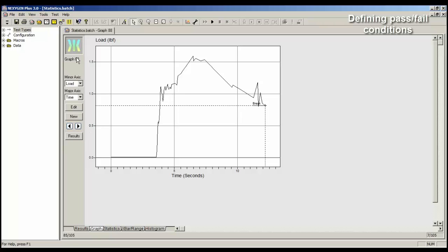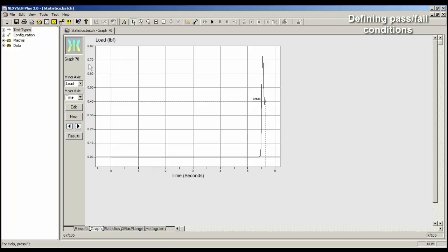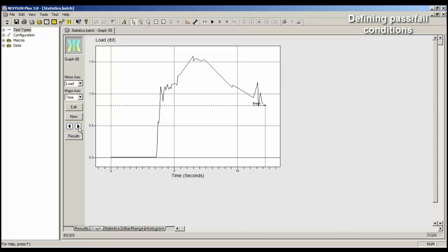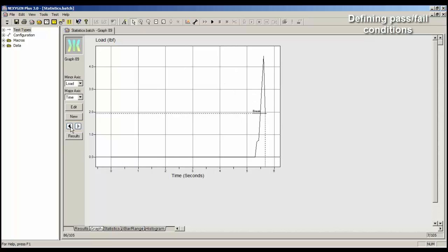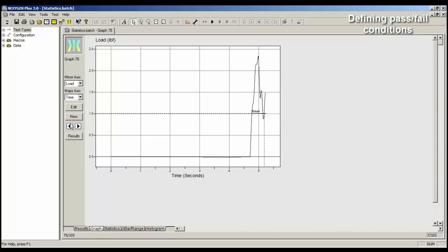Now normally, if I don't filter my data, if I click on view the previous graph, I will go to graph number 87. But I have filtered my data, so when I click on the previous graph, it's actually showing me the previous failure, and in this case it's number 78. If I click on it again, it's the failure before that failure, and it's graph number 70. So we can see it's quite easy to move through the failed tests to examine the graphs.